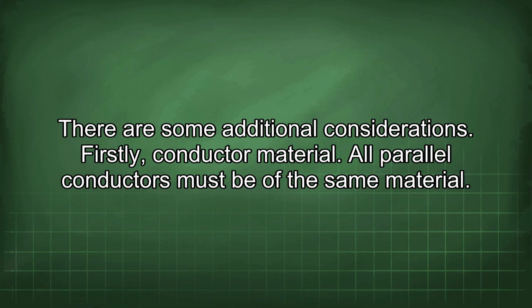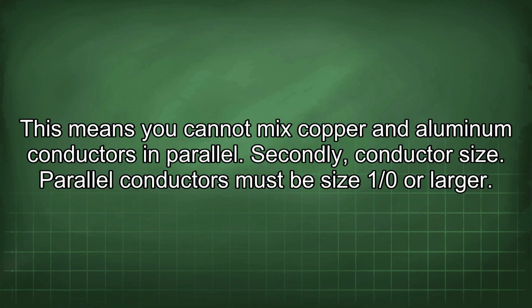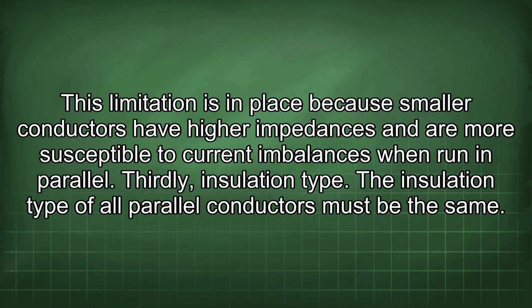Firstly, conductor material. All parallel conductors must be of the same material. This means you cannot mix copper and aluminum conductors in parallel. Secondly, conductor size. Parallel conductors must be size 1/0 or larger. This limitation is in place because smaller conductors have higher impedances and are more susceptible to current imbalances when run in parallel.